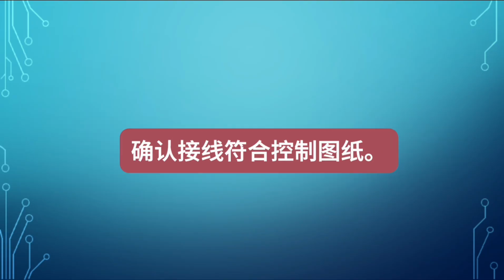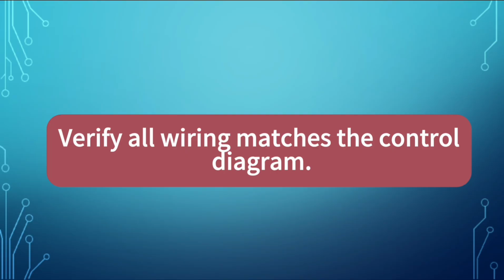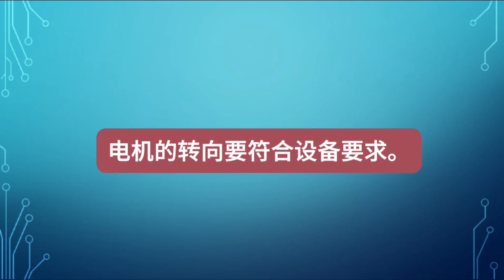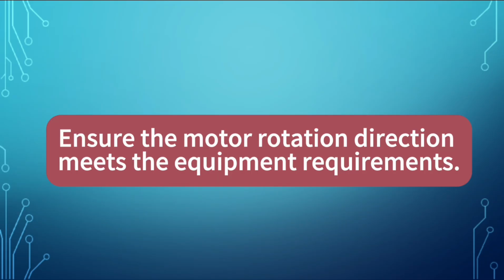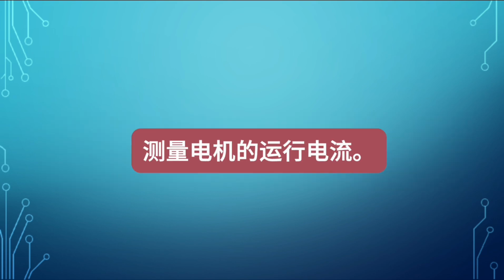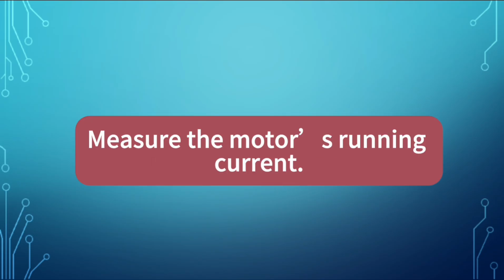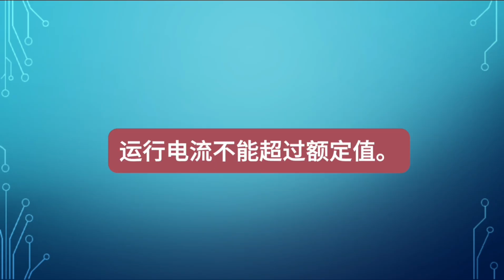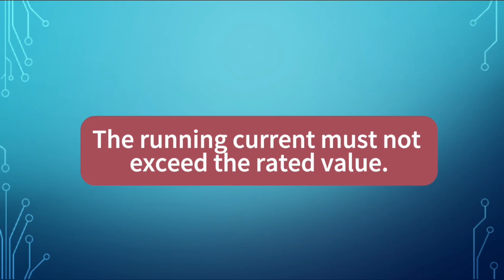Verify all wiring matches the control diagram. Ensure the motor rotation direction meets the equipment requirements. Measure the motor's running current. The running current must not exceed the rated value.